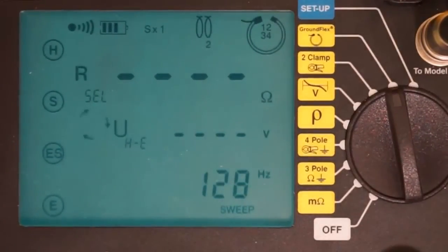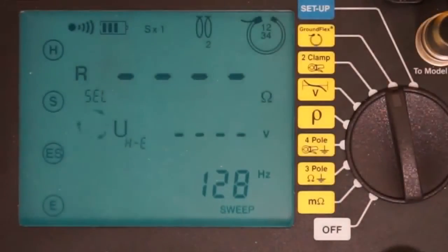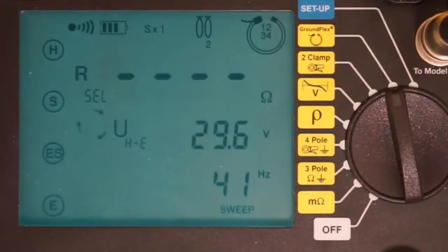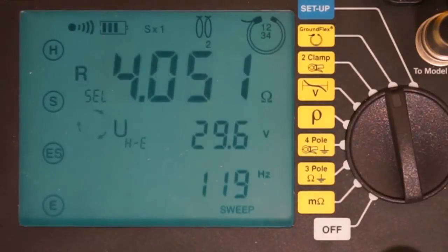To establish a baseline, the Model 6472 initially performs a measurement at 128 Hz. It then cycles through the range of frequencies from lowest to highest. Note that since we are measuring inductance rather than resistance, the measurement increases as the frequency does. The results appear in the display screen.